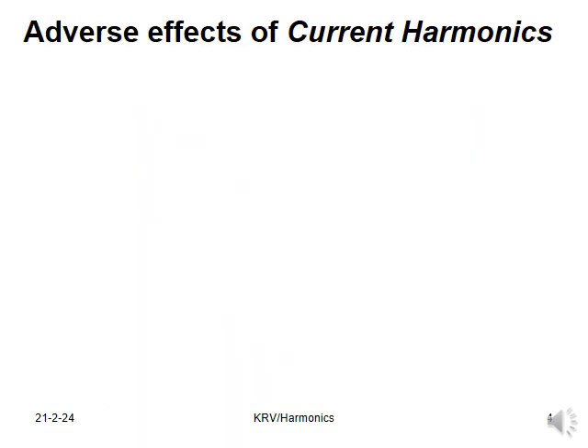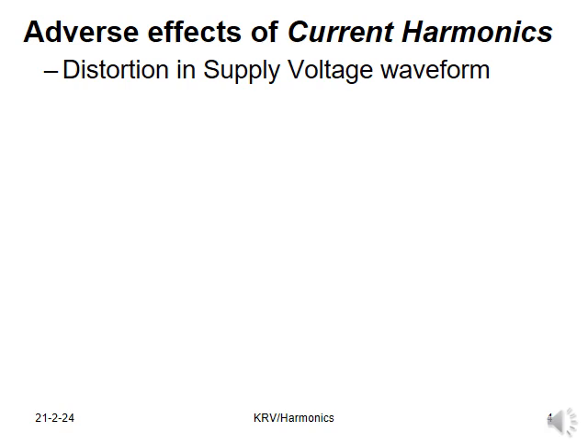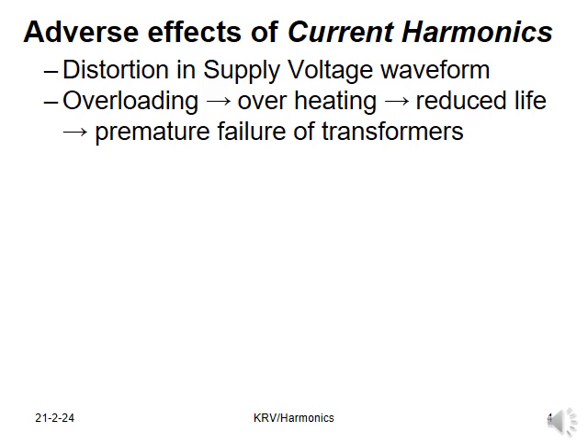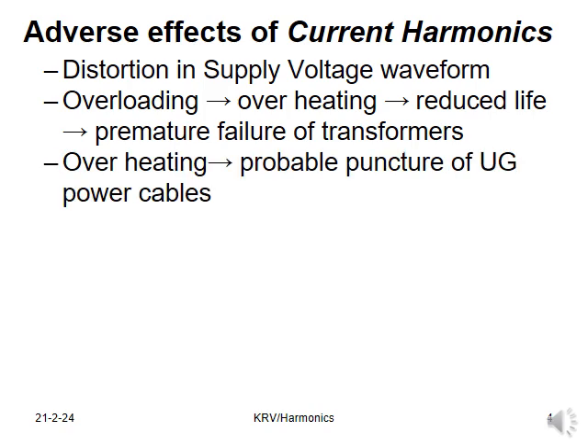What are the adverse effects of harmonics? There are many. They produce distortion in the supply voltage waveform. Due to the high frequency components, they cause overloading, overheating, reduced life, and probable premature failure of the transformers supplying power to the installation. Due to a concept called triplen harmonics, they cause overheating and probable puncture of UG power cables.